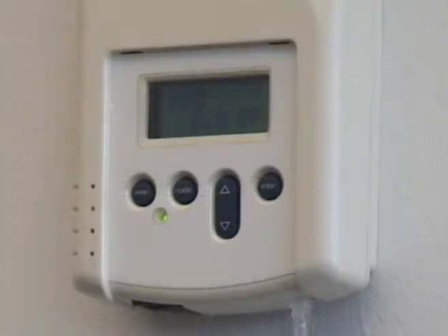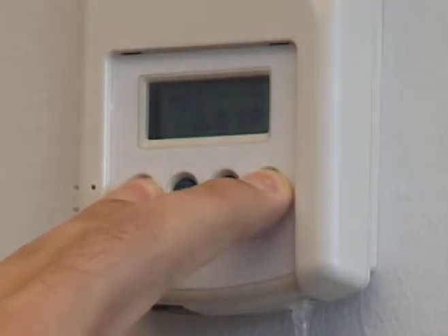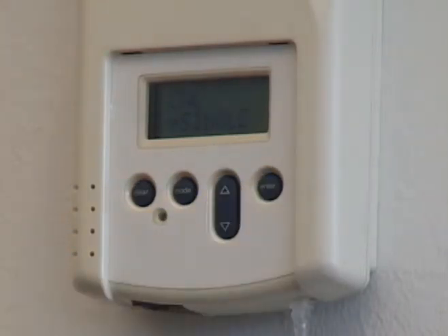Step 2. Zero calibrate. To initialize the VaporStat's zero calibration, press and hold both the Enter and Clear buttons on the VaporStat until the display reads Cal Single. Next, press the up arrow or down arrow button. The VaporStat display reads Cal 0. Press Enter to start zero calibration. The display will continue to read Cal 0 and the green LED will blink for the duration of the calibration. The calibration will complete automatically and will take approximately 8 minutes. When the calibration is complete, the display will automatically return to normal reading and the green LED will stop blinking.